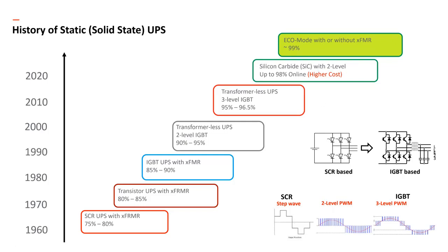Most UPSs today are around 96.5, give or take, between 96.5 and 97 in online efficiency. With silicon carbide, which is the next generation semiconductor, we can get up around 98, but they're very expensive. So there's no doubt that will be the future, but they're not competitive price-wise yet. It doesn't justify the gain in efficiency. And then, of course, there's the big gorilla in the room, the green one on top. You can get to 99%, but now you're in bypass. Most UPSs, all ABB UPSs, can do that, but very few customers want to do that. That's not why they bought a UPS.